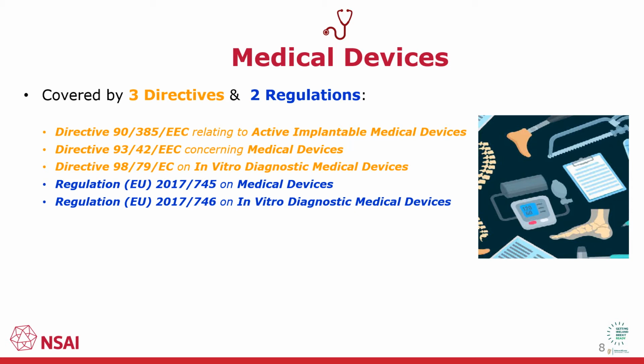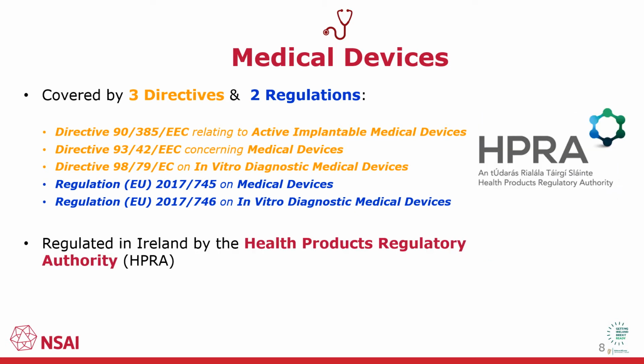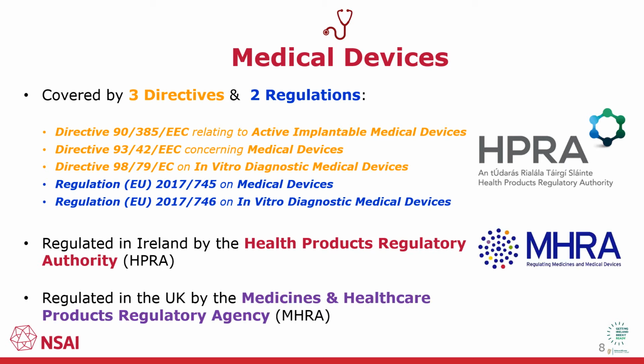medical device regulation. In Ireland, the Health Products Regulatory Authority, HPRA, is the competent authority for the regulation of medical devices. In the UK, its equivalent is the MHRA. Now, 2 years ago, the MHRA had stated that they would recognise the CE mark for medical devices for 2 years post-Brexit. Currently, we do not know if this is still the case at the end of the year. Their website now states that they are going to produce a guidance document.